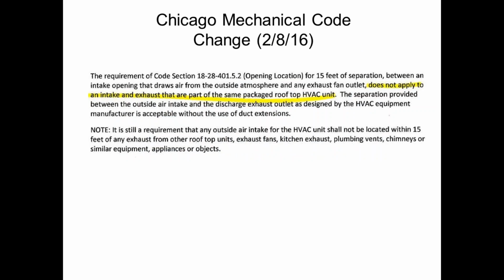One other thing I want to point out with the City of Chicago Code while we're talking about it, that's not directly related to the Energy Code, but it is very related to packaged rooftop units. Historically, the city has required you to add 15 feet of external ductwork to packaged rooftop units for the outside air intake to get that intake away from the power exhaust on the unit or the heat exhaust and all those kinds of things. That is no longer a requirement of the code. For the past 13 months, you do not have to do that in the City of Chicago anymore if it is a packaged rooftop and it is properly rated. So you do not have to have that 15-foot extension on there anymore.